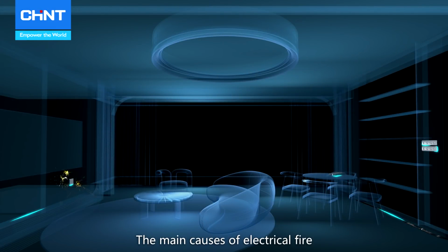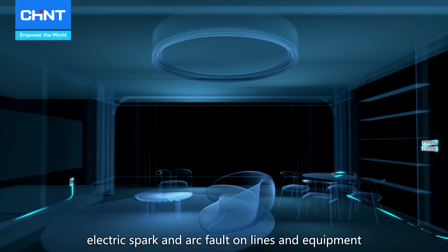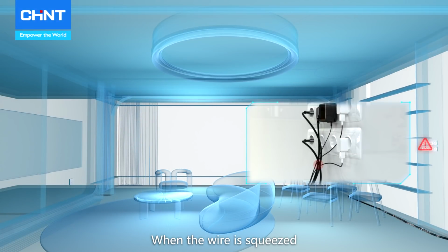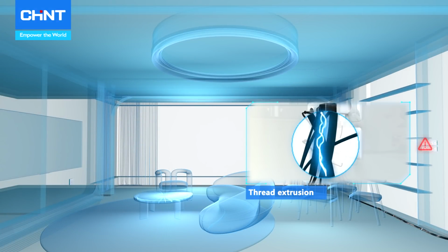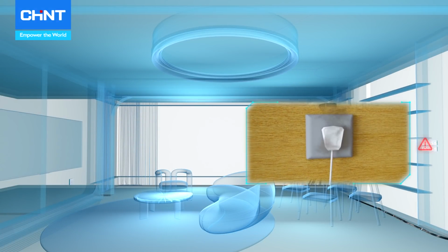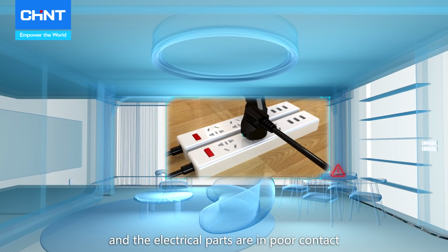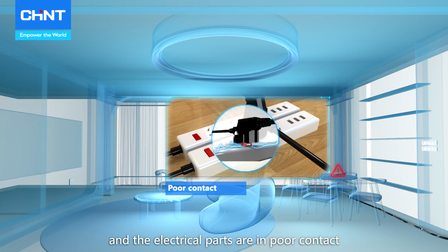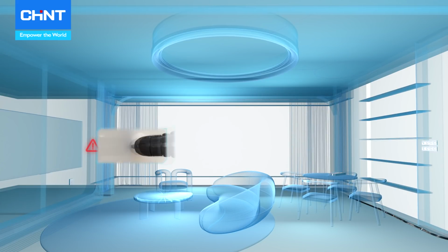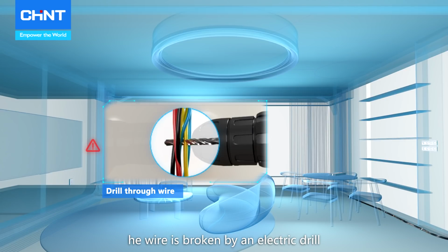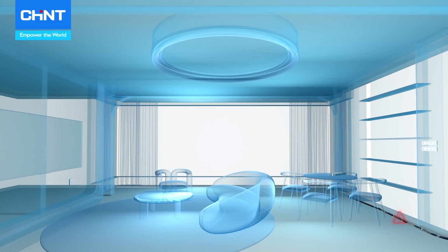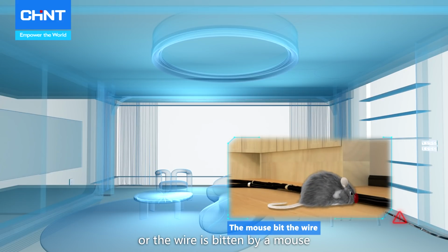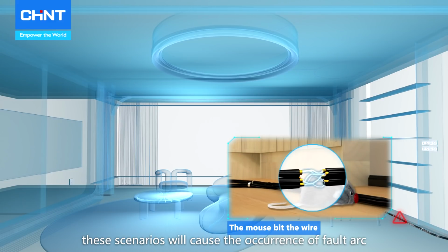The main causes of electrical fire are line overcurrent, electric spark, and arc fault on lines and equipment. This happens when the wire is squeezed, the circuit is aged, and the electric parts are in poor contact, when the wire is broken by an electric drill, or bitten by a mouse. These scenarios will cause the occurrence of fault arc.